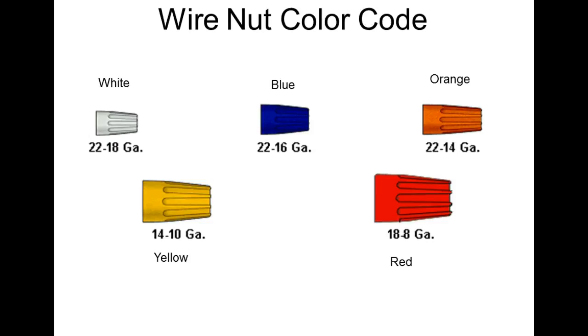So this right here might be rated at 8 gauge, but if we look at the box it says 8 gauge 2 wires. And then it might say 12 gauge 10 wires. So when you get these things, the color doesn't indicate the minimum, it indicates the maximum gauge you can put on there, but the minimum gauge is determined by how many of those you use, right?